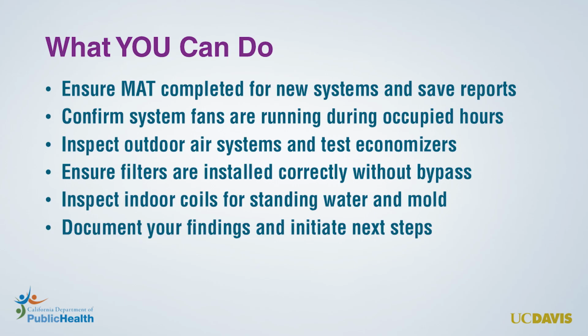In this module, we reviewed a number of important inspections you can make to maintain your HVAC systems and identify problems. Let's review these briefly. Ensure that mechanical acceptance testing is completed for new systems and save the reports for future reference. Confirm that HVAC system fans are running during occupied hours. Inspect outdoor air systems and test economizers to make sure dampers are moving as expected.